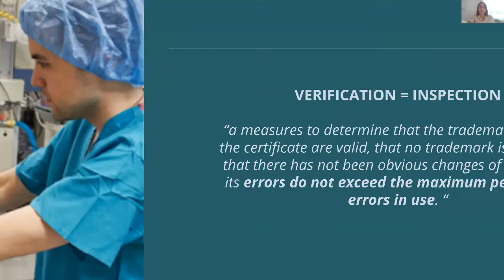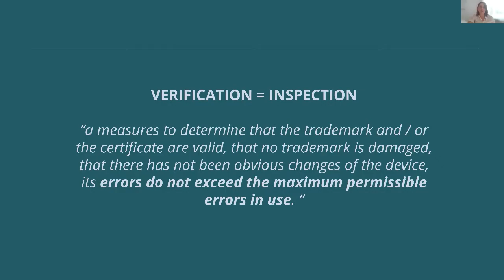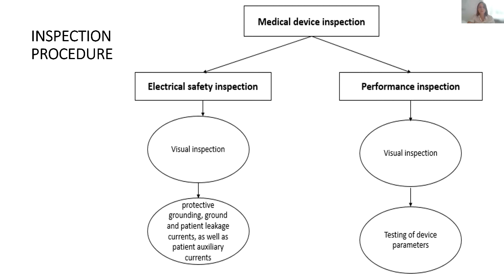The goal of every inspection procedure is to determine its output error. That is actually what the inspection is. We determine that the error in measurement of the medical device does not exceed the maximum permissible error in use. For this, we use a procedure. First, electrical safety inspection, and then performance inspection. We do a visual inspection of a medical device, and we test the device parameters as they have been defined.